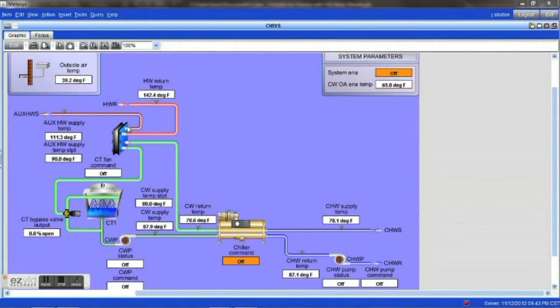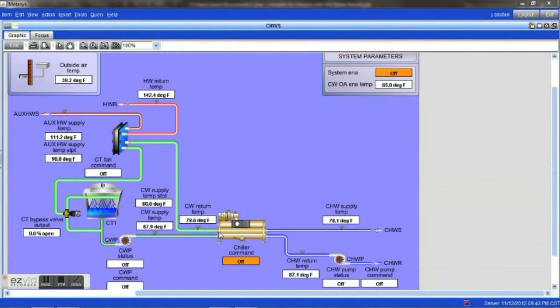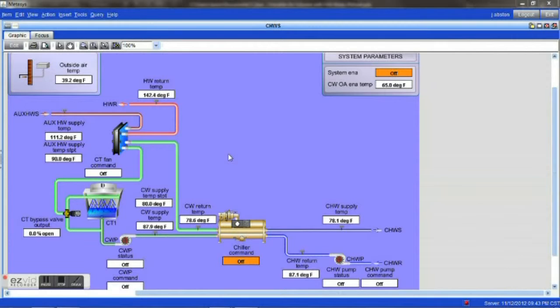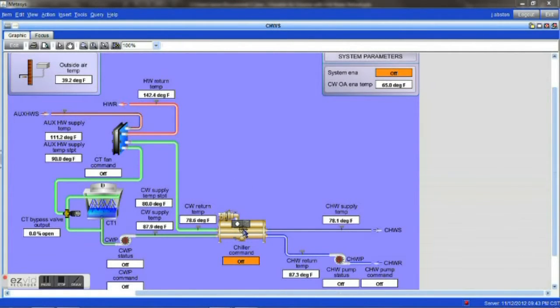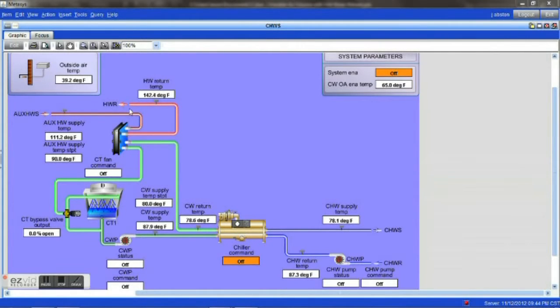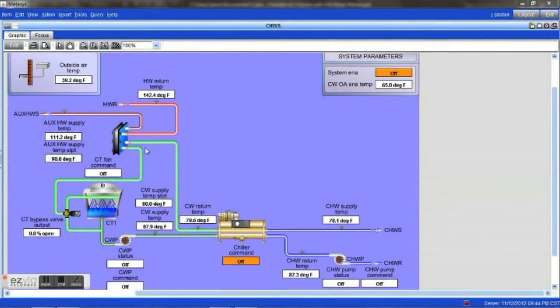Now, there are some things that you need to consider in a system such as this. One is, you need to make sure that the system is adequately sized. Most of the time, these chillers are. However, that is just something that you will want to truly consider, that the chiller itself will produce enough heat for the reheat system. If it will not, you will need some other type of heat source as well, such as a boiler. But most of the time, these chillers, the very large ones especially, have no problem generating that extra heat.